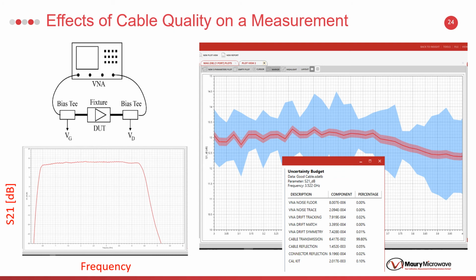amplifier. With the less stable cables, the measurement uncertainty is plus or minus 1 dB between 3 to 4 GHz, while the stable set of cables is less than 0.1 dB. If we look at the uncertainty budget, we can see that 99% contribution to uncertainty is coming from the cables, which tells us that cables are a major source of uncertainty in the measurement.